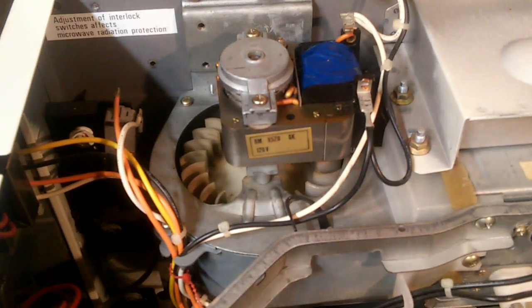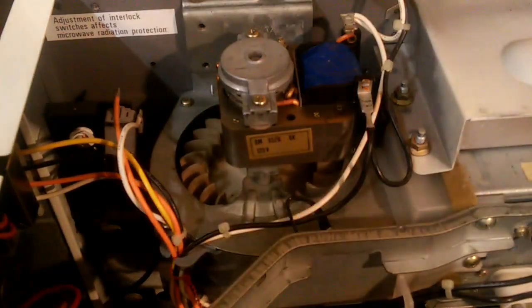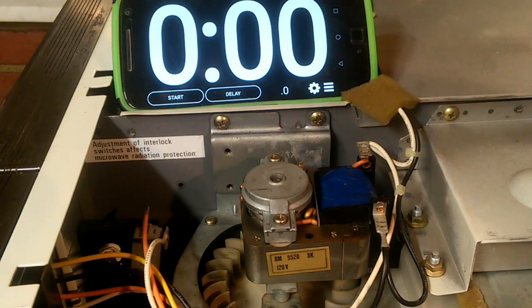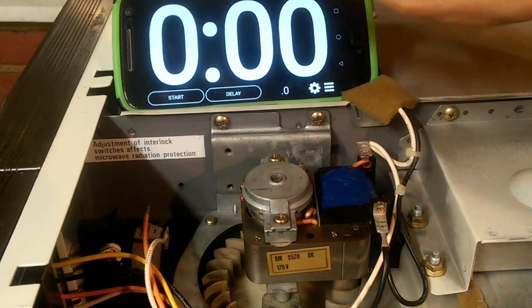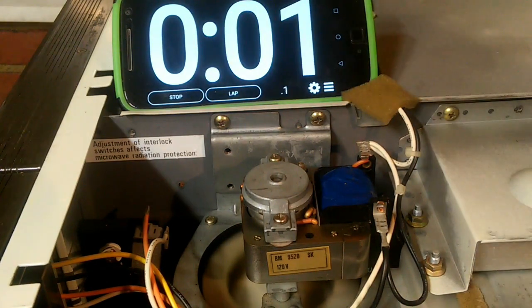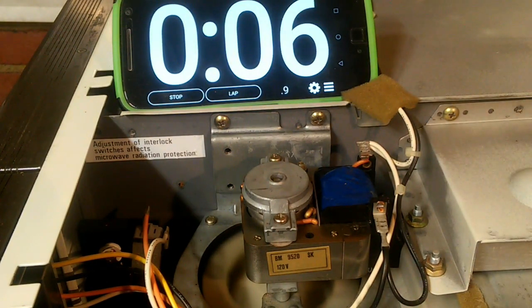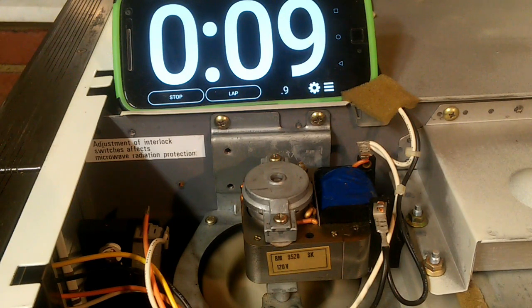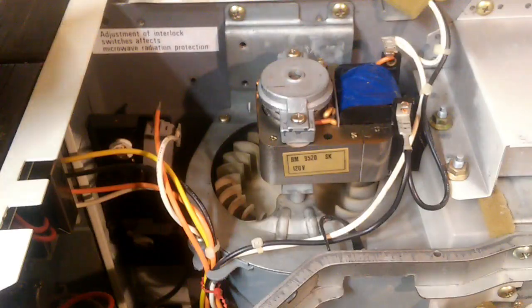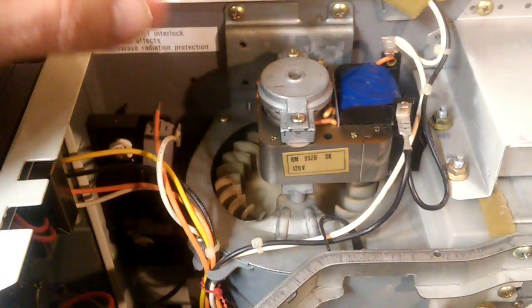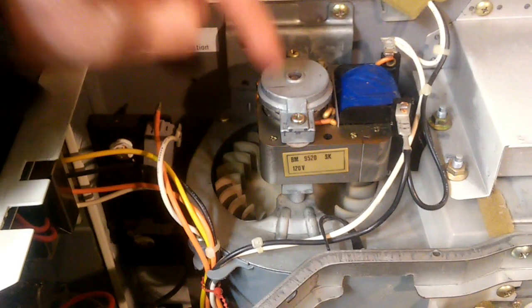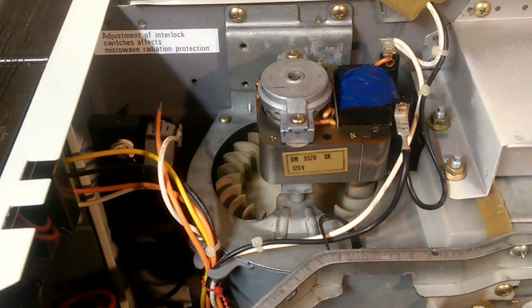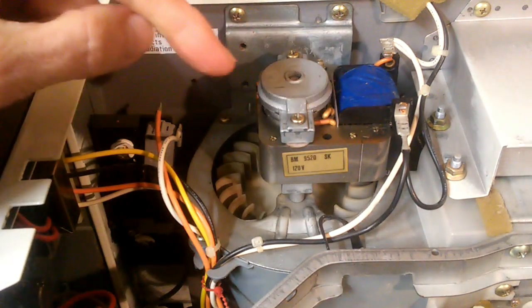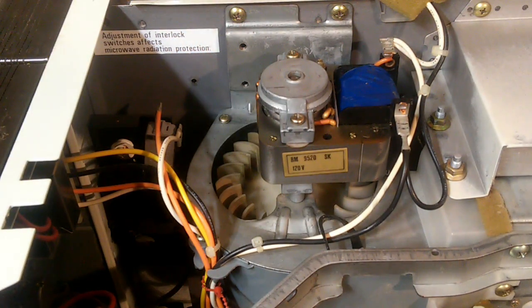Now that it's been warmed up, it will spin up much quicker. We'll start it up again and see how long it takes. Okay, in only 10 seconds it goes to full speed. Even in a colder room, once the fan itself warms up, and presumably the lubricant too, it spins up to full speed immediately. But coming from a cold start at room temperature in the mid-60s, it takes a full 1.5 minutes before the fan spins fast enough to turn the microwave stirrer.